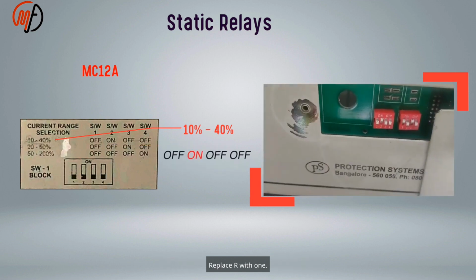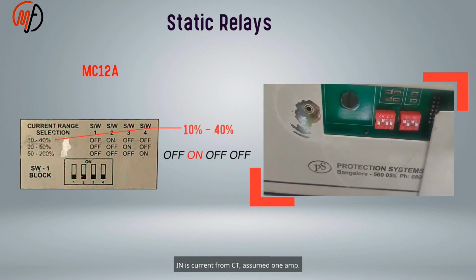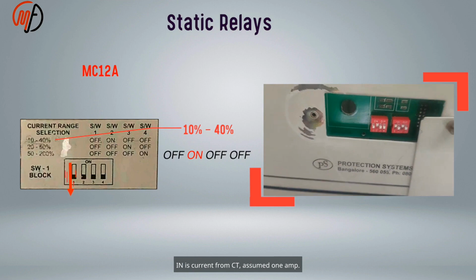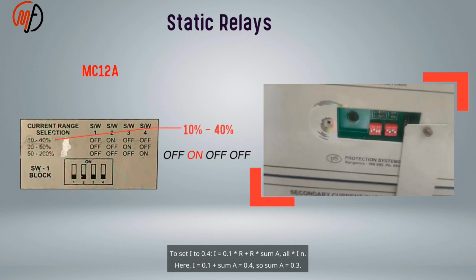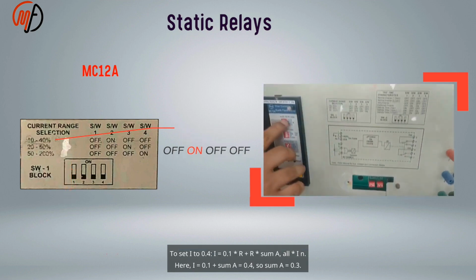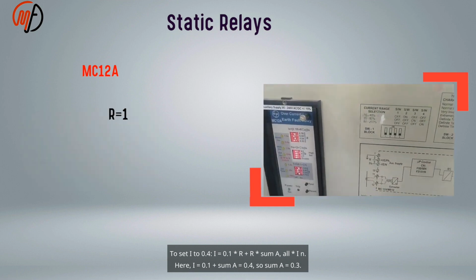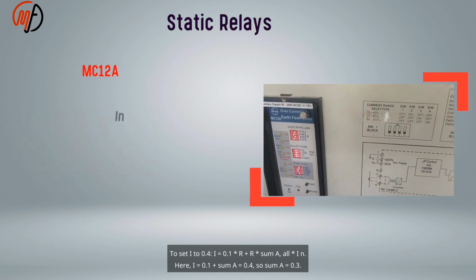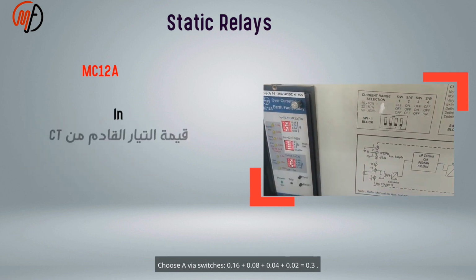Assume 1 amp. To set I to 0.4, I = 0.1 R plus R times the sum of A, all times IN. Here, I = 0.1 plus sum A = 0.4, so the sum of A = 0.3. Choose A via switches: 0.16 plus 0.08 plus 0.04 plus 0.02, verify 0.3.